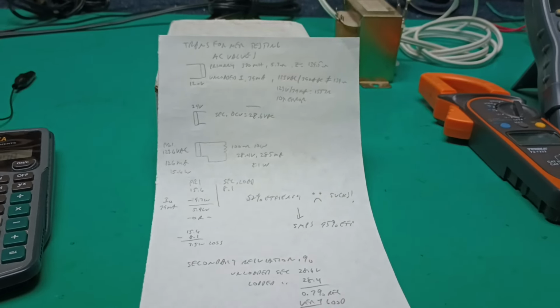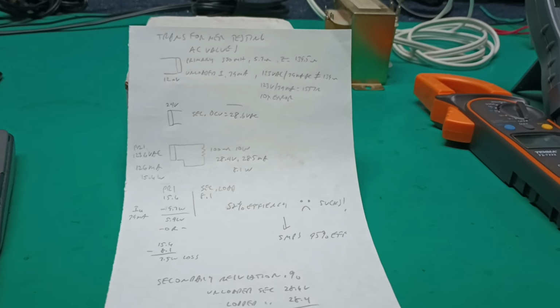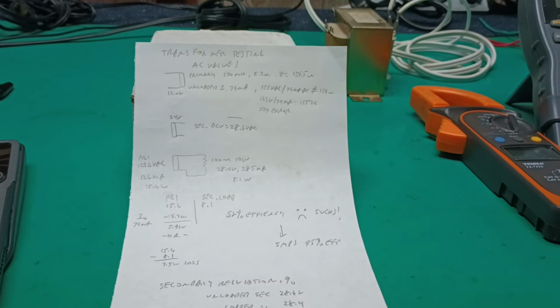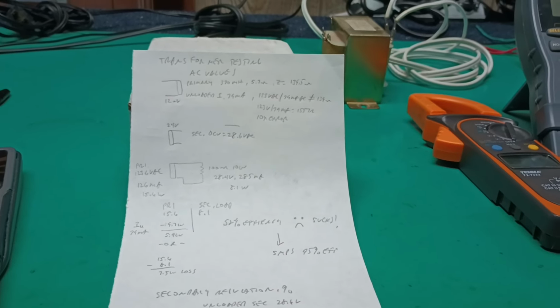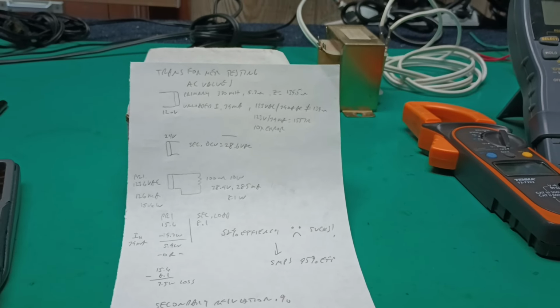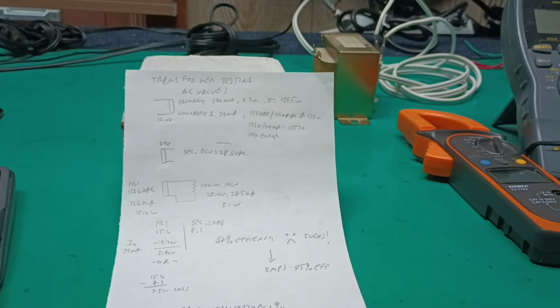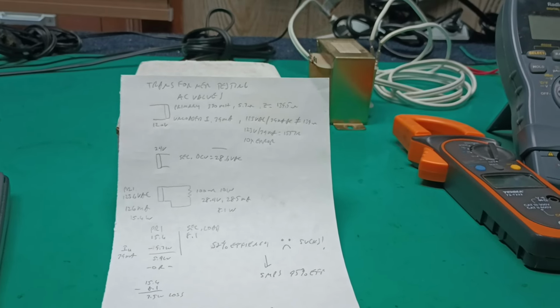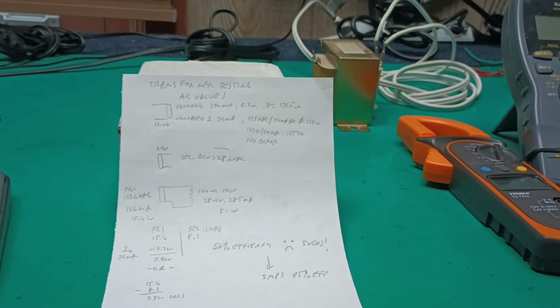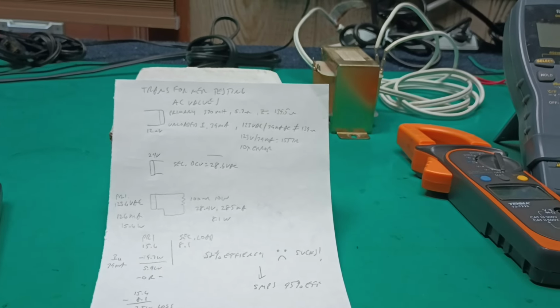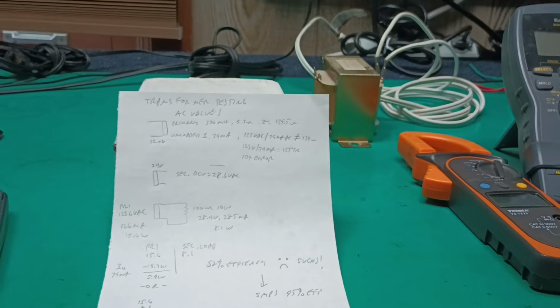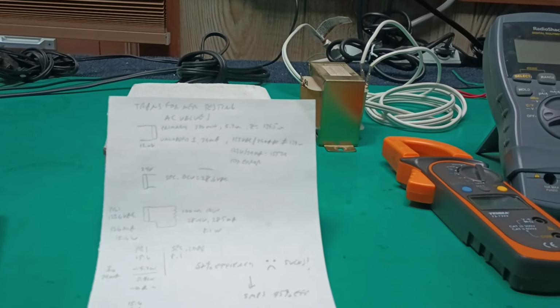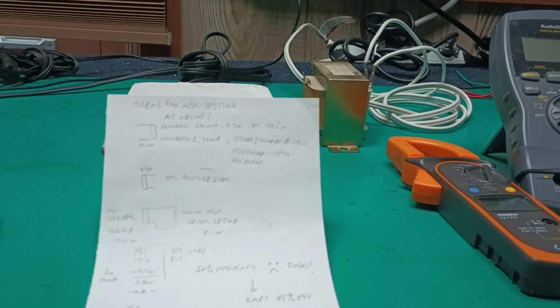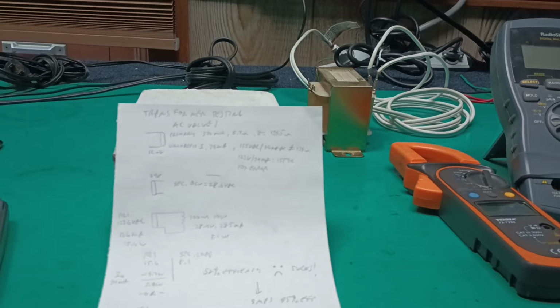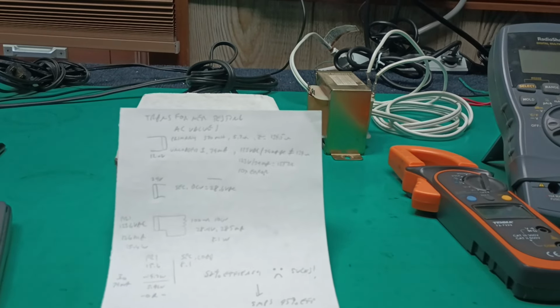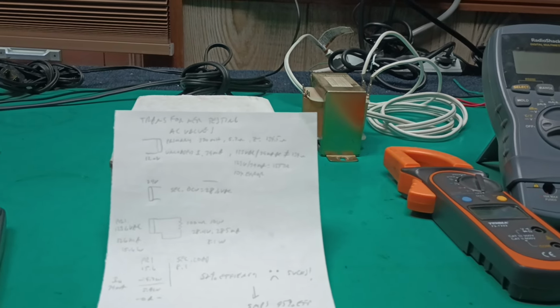Interesting thing to note, the apparently grossly incorrect reading of primary inductance when an LCR meter, which I've measured at 5 kilohertz on some certain range, was connected to that transformer. That transformer is either iron or cheap steel laminates. Apparently that core has shunted out and consumed that 5 kilohertz energy. What that means is that the 60 hertz transformer has effectively become an RF choke. Now, 5 kilohertz is not RF yet, but it's a 5 kilohertz square wave, and that has RF components. So what we've got here is effectively an RF choke. And that's how line reactors work. The old ones are just inductors wound on iron cores.